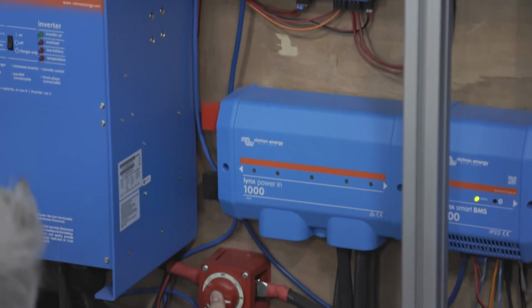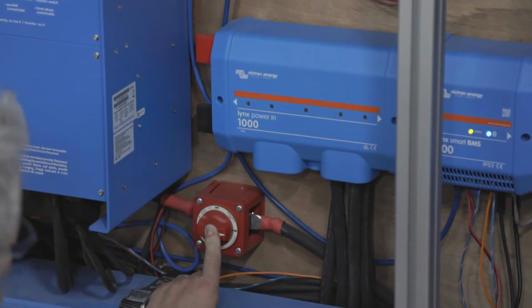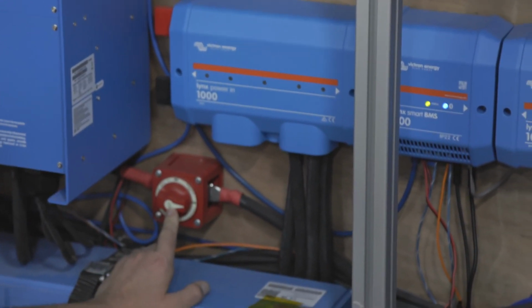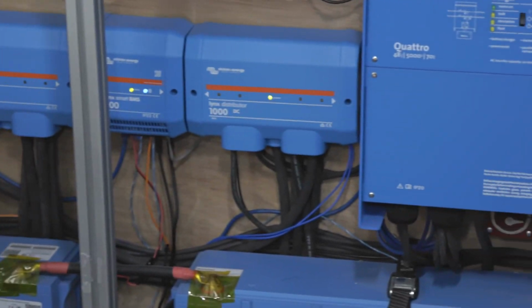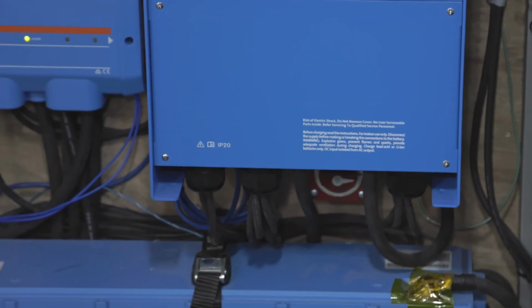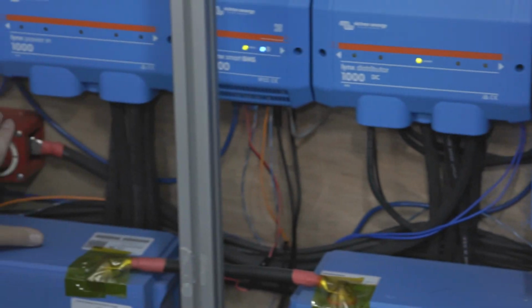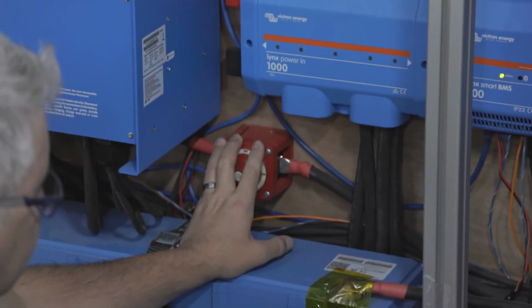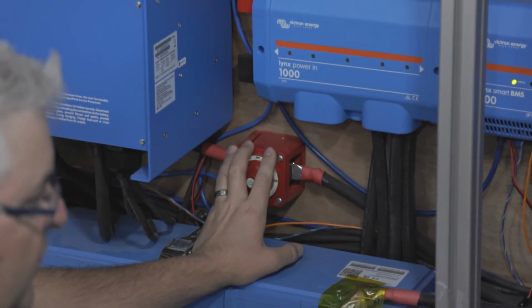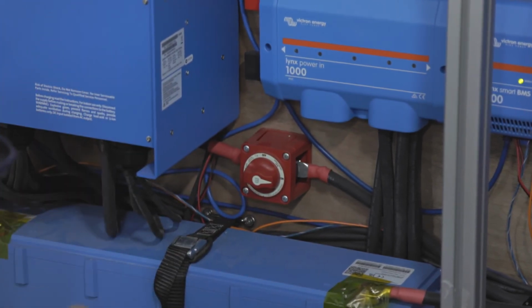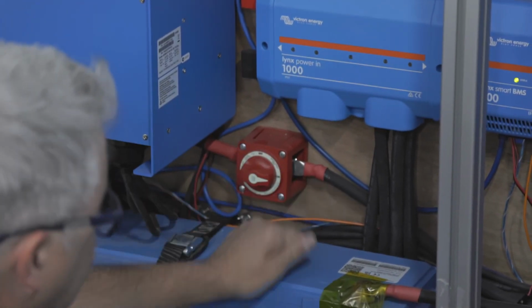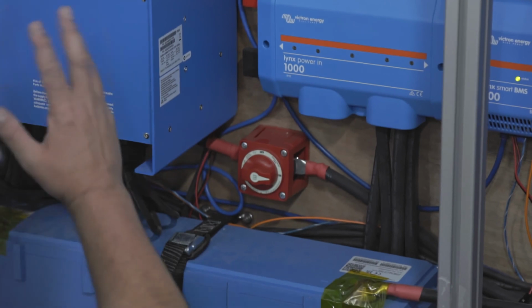There's a red switch for each inverter. Basically, it is a battery disconnect switch. The DC power that comes from the batteries goes into this switch to feed the inverter. That's here more for maintenance purposes, not operational use. If an inverter failed and we needed to replace it, we could close that switch, isolate it, and safely work on it.